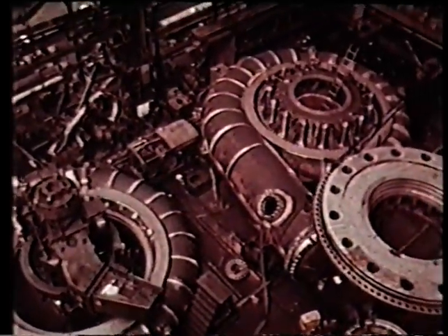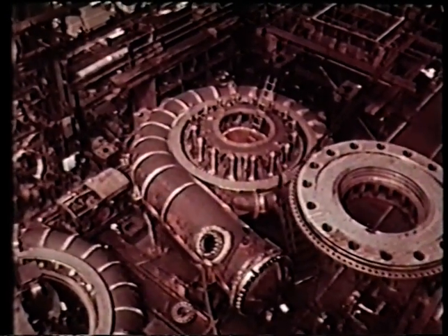The top and bottom covers are cast in steel and fitted with renewable runner seal wearing rings. These covers also form bearing units for the water guide vanes. In one pair, the covers have fitted locking bushes for use when pumping, actuated by high pressure oil.